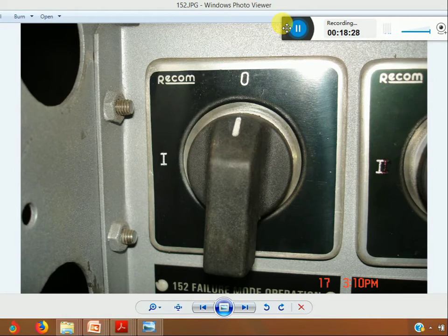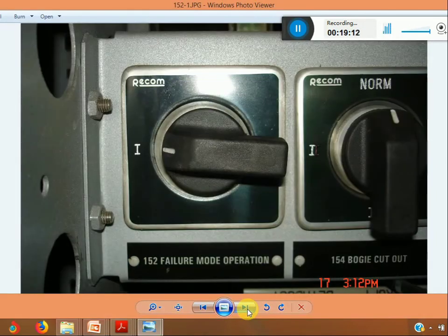152, failure mode switch with 2 positions, 0 and 1. 0 position is normal. In normal position, smooth control of TEB will respond. In case of TEB failure, handle operation failure, or in case of a message F1703P1 or F1803P1, TEB not responding, we have to change the switch to one position. If you keep this switch to one position, by rotating it anti-clockwise, the TEB will respond in 3 steps: 33%, 66%, and 100%.